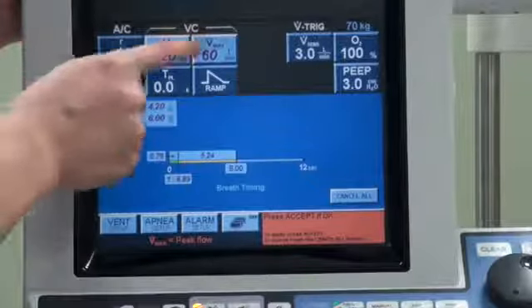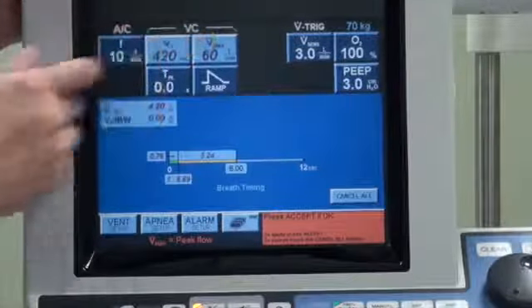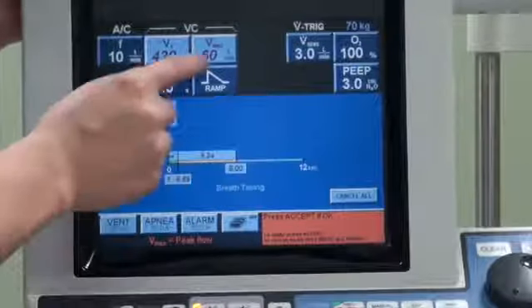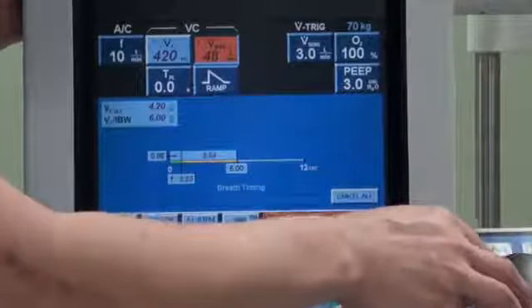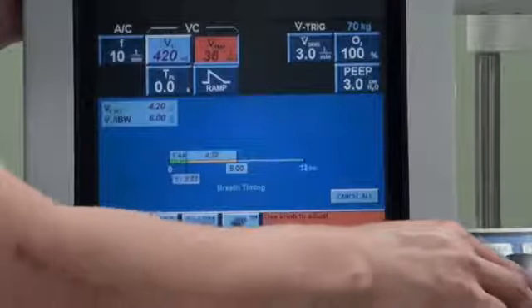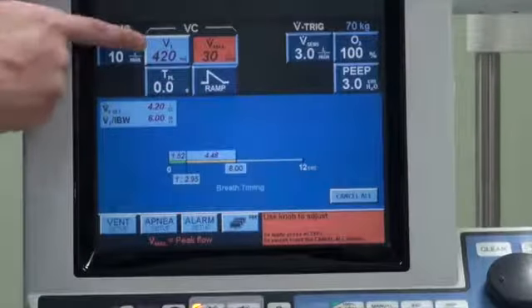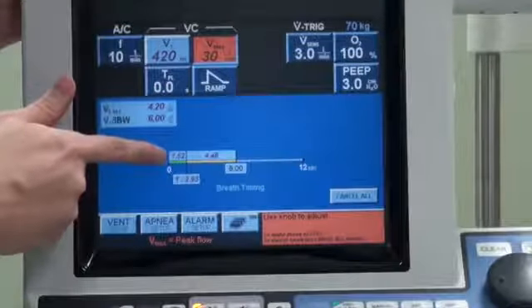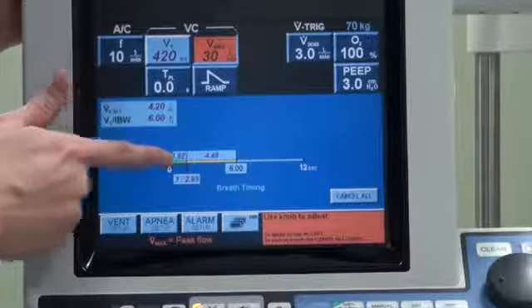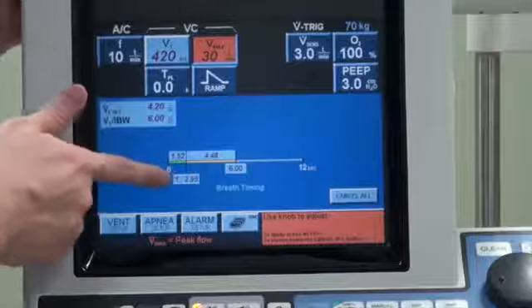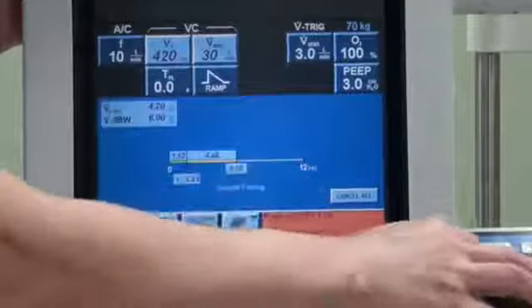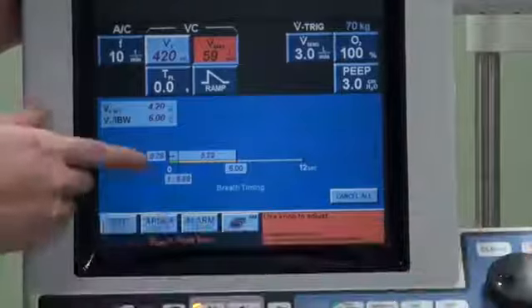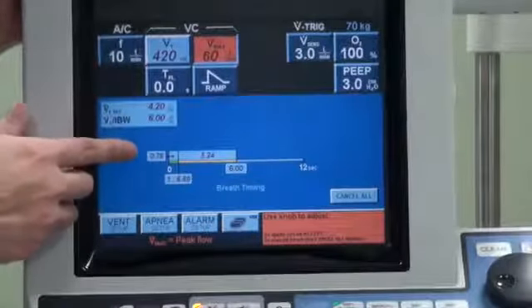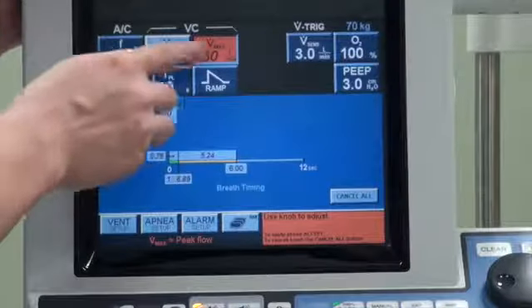You will notice that when we change either the tidal volume, frequency, or the flow, the I to E ratio will change. So let's say that you want to deliver the breath at a very, very slow flow, say 30. You'll notice that it takes a long time for the ventilator to reach the target volume, and the inspiratory time is now 1.52 and expiratory time is 4.4. That gives us an IE ratio of 1 to close to 3. But if you want to deliver the breath much faster, at double the flow, you'll notice that the inspiratory time has shortened, and that gives you an I to E ratio of 1 to 6.